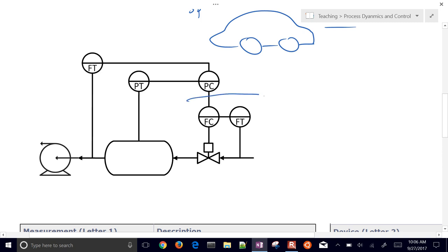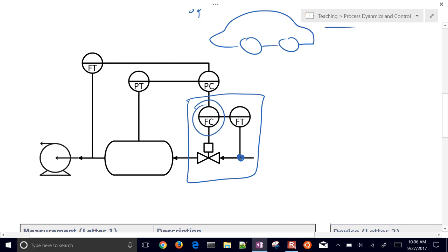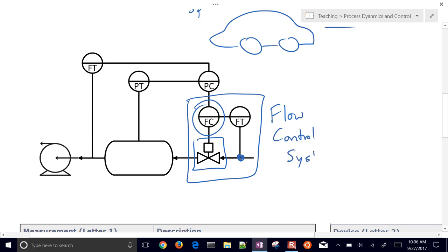Looking at a specific example: a flow transmitter measures the flow at a location, and based on that measurement, a flow controller adjusts a valve open or shut to maintain a certain flow setpoint. This is a flow control system made up of a sensor, an actuator (the valve), and a controller — the three required elements for control.